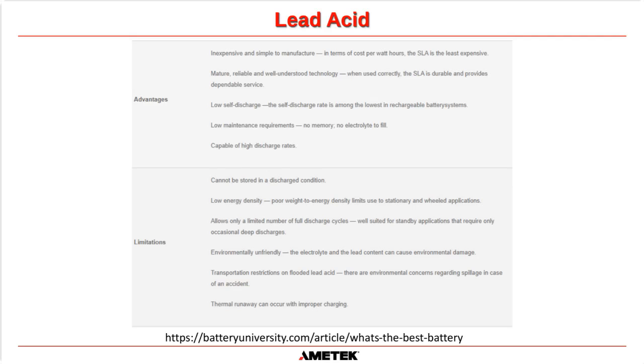The limitations: they cannot be stored in a discharged condition. If you discharge a lead-acid cell below 1.6 volts, then it pretty much can't be relied upon after that. So you cannot discharge it down to 0 and store it and then recharge it back up again. It also has low energy density. Basically, it has poor weight to energy density limits. So therefore, you need a much bigger physical battery, compared especially to a lithium-ion battery, to get the power that you want.